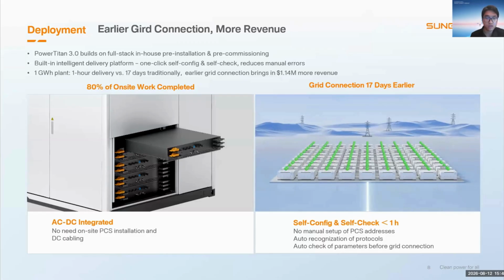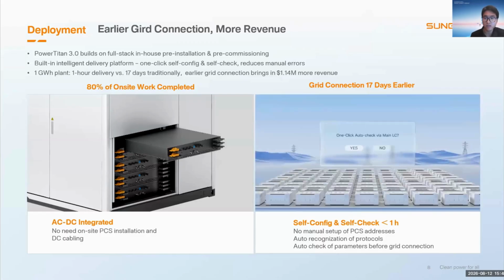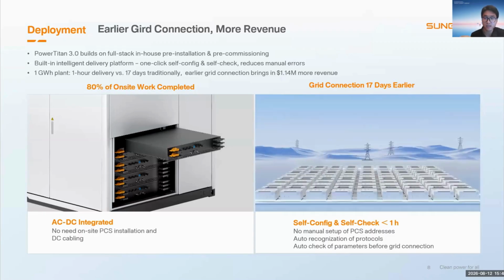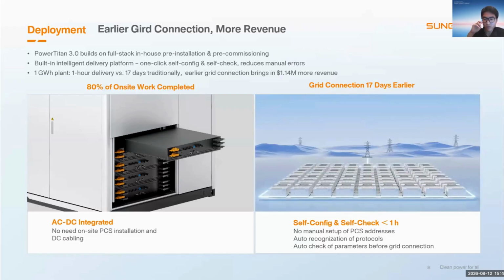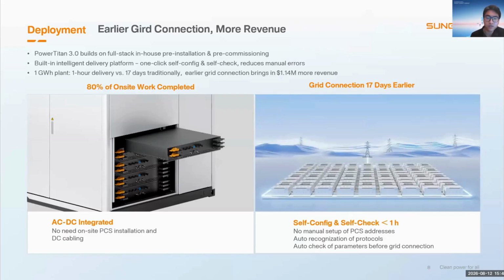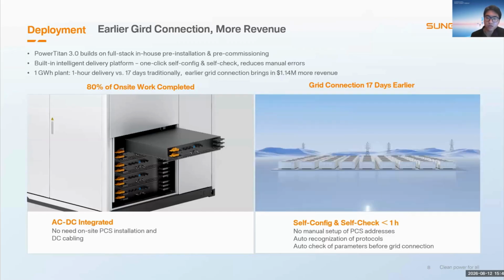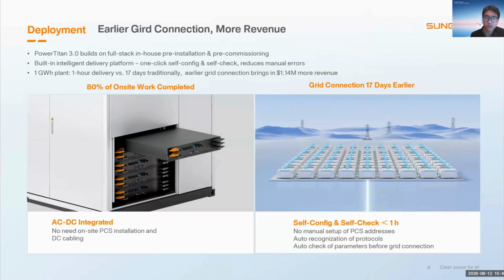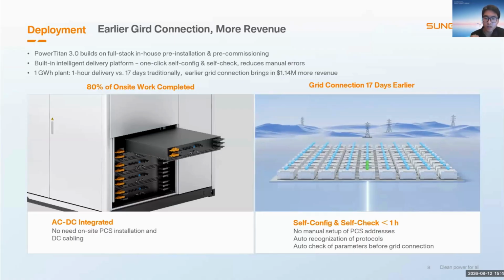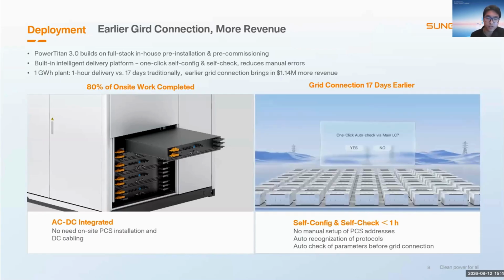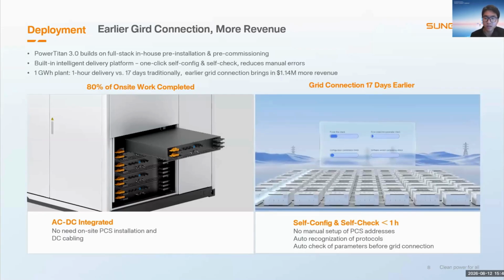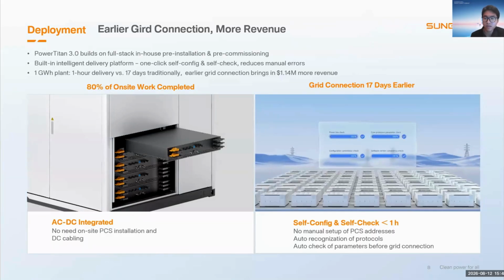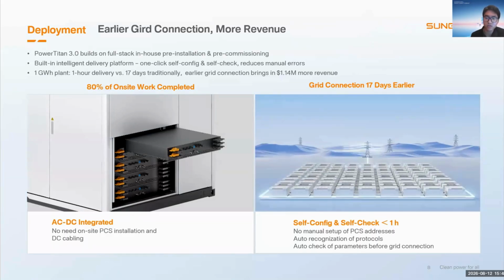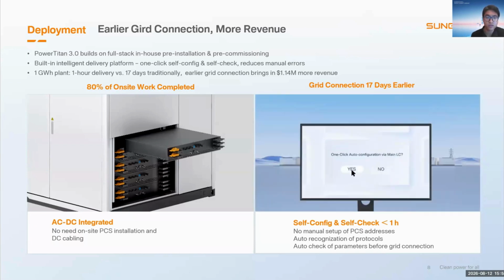So in a traditional gigawatt-hour plant, engineers need to configure and commission hundreds of PCSs one by one. And this process usually takes at least 17 days. With our innovations such as self-configuration and self-check functions, the entire plant configuration and inspection can now be completed within 1 hour. This means the plant can be connected to the grid much more easily and start generating revenue much sooner.